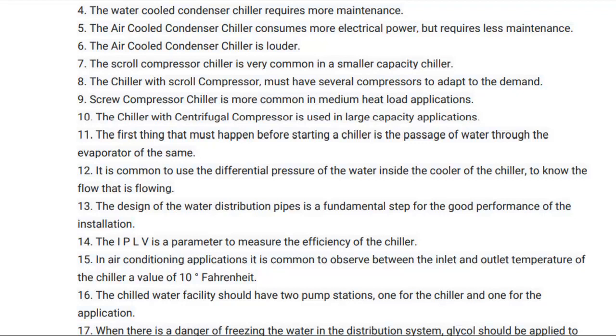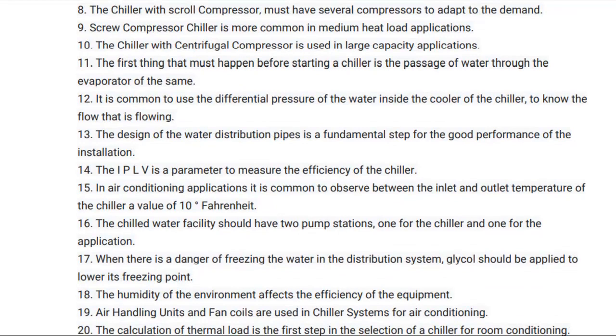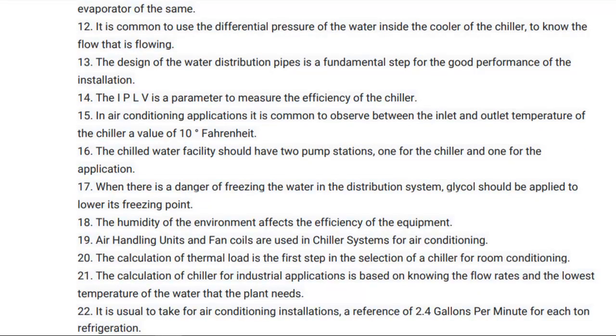11. The first thing that must happen before starting a chiller is the passage of water through the evaporator of the same. 12. It is common to use the differential pressure of the water inside the cooler of the chiller to know the flow that is flowing. 13. The design of the water distribution pipes is a fundamental step for the good performance of the installation.